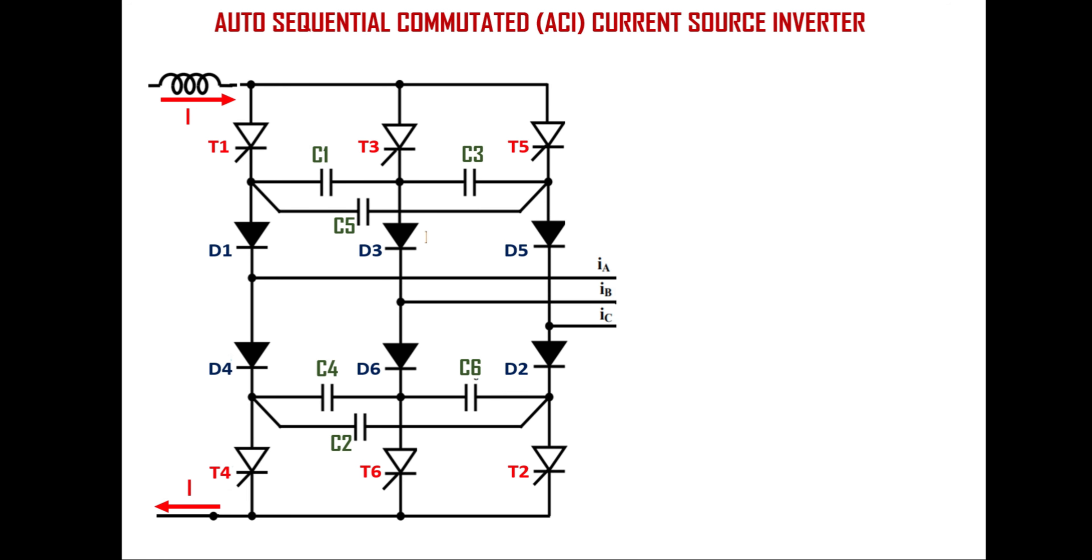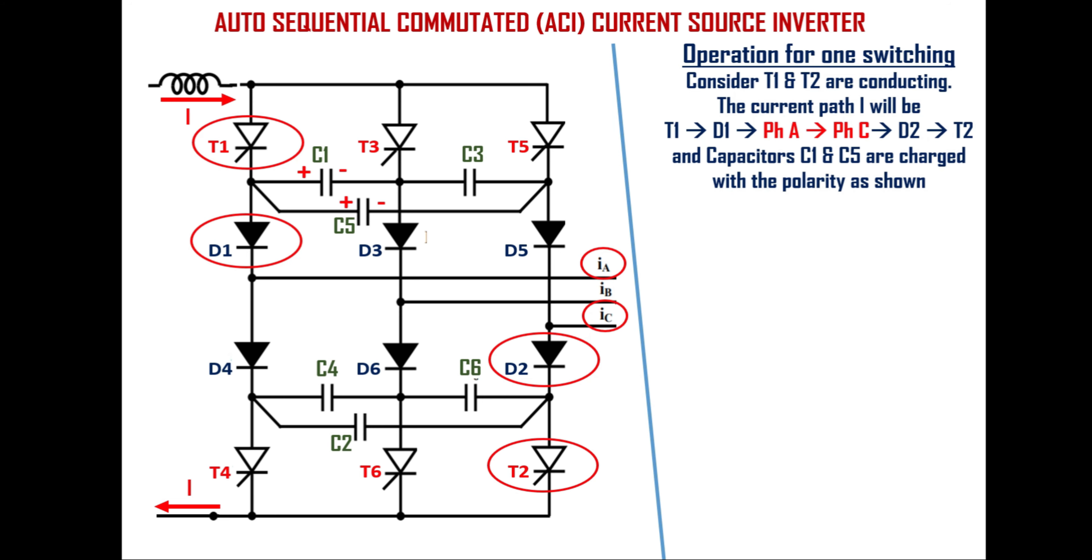In the steady state the sequence of events will be identical at each switching. So let's examine the inverter operation for one switching. Thyristors are numbered in accordance with sequence in which they are fired. Now consider thyristor T1 and T2 are conducting initially. Then source current I will flow through the path of thyristor T1, diode D1, phase A, phase C, diode D2, thyristor T2 and back to the input source.